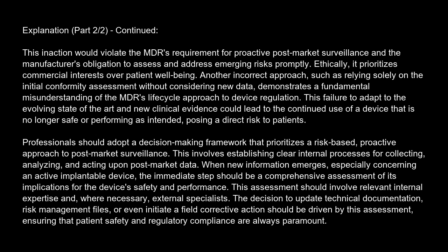Professionals should adopt a decision-making framework that prioritizes a risk-based, proactive approach to post-market surveillance. This involves establishing clear internal processes for collecting, analyzing, and acting upon post-market data. When new information emerges, especially concerning an active implantable device, the immediate step should be a comprehensive assessment of its implications for the device's safety and performance. This assessment should involve relevant internal expertise and, where necessary, external specialists. The decision to update technical documentation, risk management files, or even initiate a field corrective action should be driven by this assessment, ensuring that patient safety and regulatory compliance are always paramount.